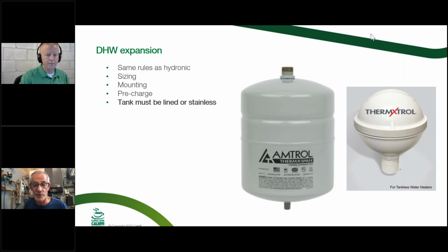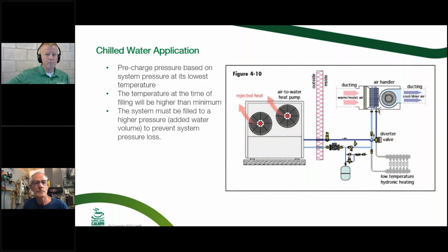I have heard of guys using these on hydronic systems, just lowering the pressure, of course, because these are typically 45 or 50 PSI pre-charge. I believe the bladders are pretty similar, so it could be used if you want to, and now you've got a lined tank again, but since they make a radiant or hydronic specific line tank, I would go that direction. All right.